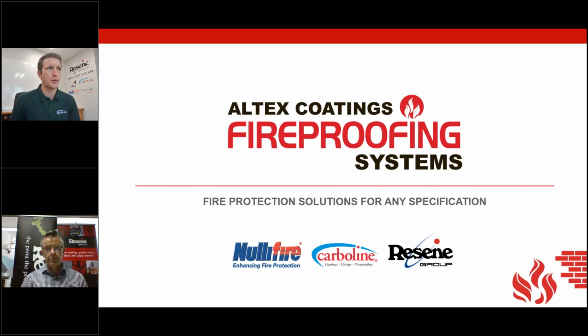Certainly with regards to the different types of construction, like the speed wall and Korok type systems that are joined to fire rated steelwork, yes, that has been looked at. I've been in conversations and been part of some of the testing with the guys from Korok, using some of our products and running some fire tests, furnace tests in conjunction with their systems, with good positive results. By using that, we've been able to offer architects and engineers some good solid advice on their design methodology in order to get past muster with regards to building consent as well. So there are different ways of attaching your Korok to your structural steel without compromising your fire rating.